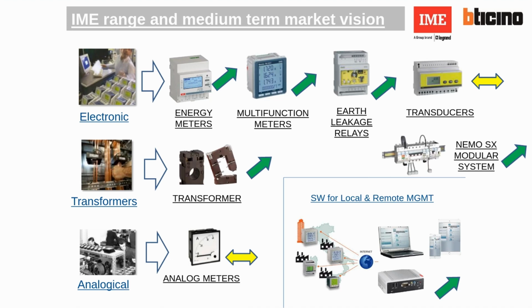Then we have a modular and scalable system that we call NEMO SX. Basically, this system permits not only to measure and meter the electrical parameters, but also to have alarms in the switchboard and to automate the switchboard, in the sense that you can have the status of the circuit breaker, whether it is open, closed, or tripped, and you can also switch on or switch off circuit breakers with a specific module. Then in the bottom right part of this slide, we have our supervision range, which is based on 3 kinds of web servers. Through a web page and an IP address, you can go on a PC, a tablet or a mobile phone and check the consumption with histograms, make benchmarks, and check the status of the breakers. So this is basically our whole range.